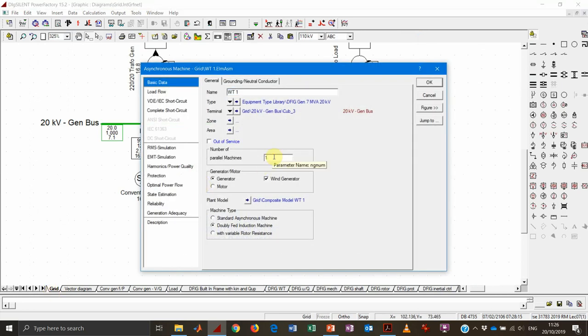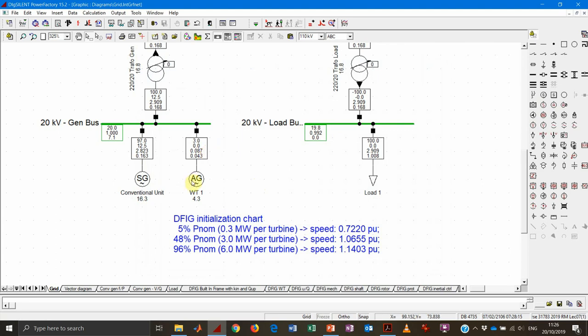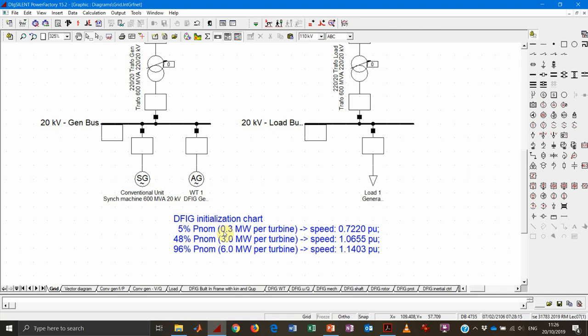Right now there is just one element modeling one individual machine, but this single machine could easily model 10 wind turbines in parallel — the dispatched power would increase 10 times. This machine is 6.25 megawatt and the minimum initial power that can be set is 0.3 megawatt. The model does not support startup from 0 megawatt, so to emulate increasing power production we should start with a very low value representing near-zero wind power and then increase accordingly.